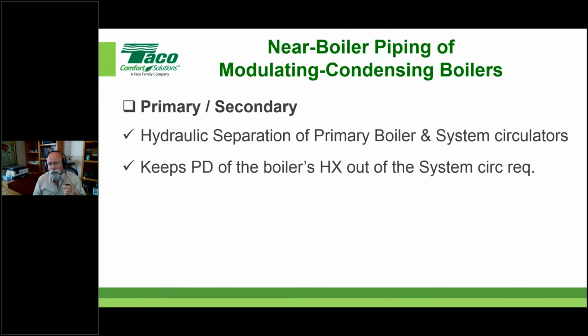Again, this came up in one of our other sessions last week. We were talking about low loss headers, use that in quotations. And where did that term come from? Well, that term came from a device that kept the pressure drop of the heat exchanger of the boiler out of the responsibility of the system circulator. Okay, and so it gave us some of the things that we're looking for. We're not going to focus on that so much today, but we call them hydraulic separators or low loss headers, but that's the reason it was called a low loss header, because we didn't want the pressure drop back in the early days of condensing equipment, which was relatively high, to be the responsibility of the system circulator.